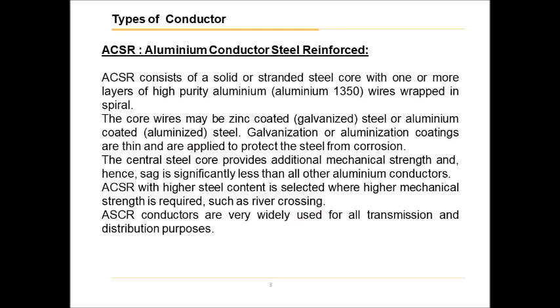ACSR — aluminium conductor steel reinforced. ACSR consists of a solid or stranded steel core with one or more layers of high-purity aluminium wires wrapped in spiral. The core wires may be zinc-coated steel or aluminium-coated steel. Galvanization or aluminization coatings are thin and are applied to protect the steel from corrosion. The central steel core provides additional mechanical strength, and hence sag is significantly less than all other aluminium conductors.